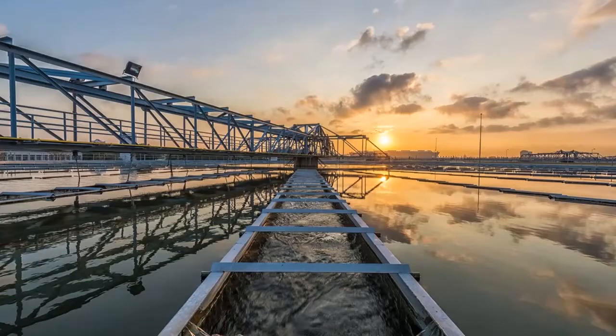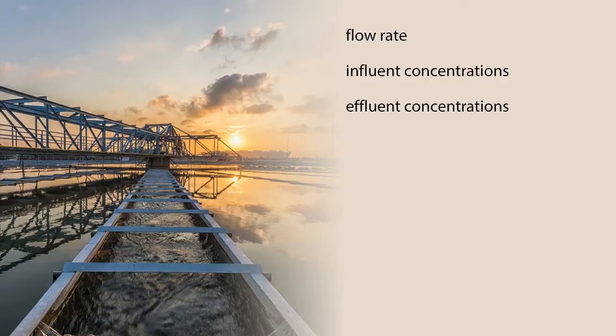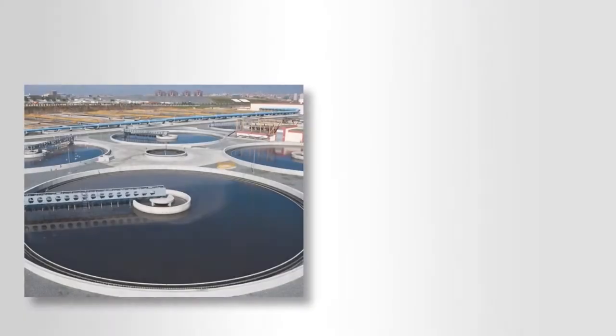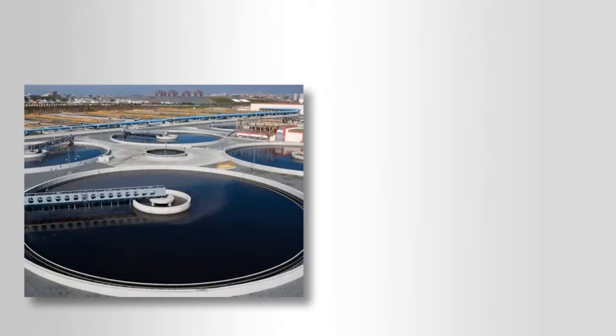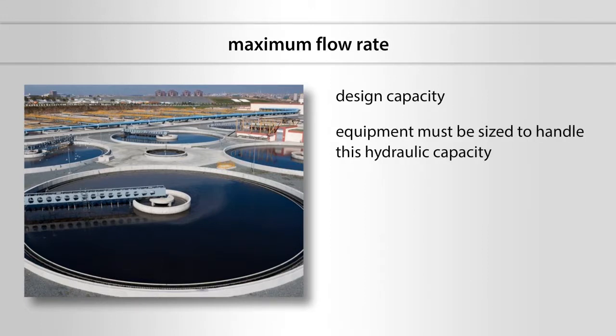The primary design criteria for any water treatment facility are flow rate, influent concentrations, and effluent concentrations. Two different flow rates must be considered. The maximum flow rate, for example 100 gallons per minute or GPM, is called the design capacity. All equipment must be sized to handle this hydraulic capacity.